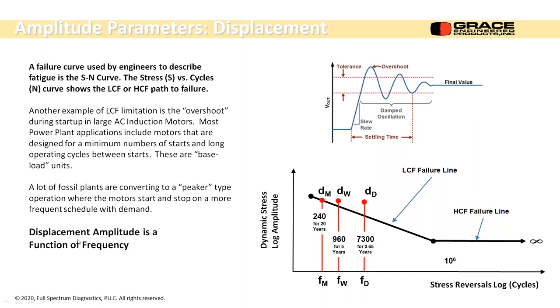Well, now these plants are starting to be used as peaker units. So natural gas plants are taking more of a baseload capability. They're turning on and off fans in fossil plants to adjust for load. What does that do? Every time we start or stop, we still have the same amplitude. We're not following that allowable curve anymore. So we'd have four times as many starts. So 960 starts. So instead of 20 years of life, we'll get 5 years of life. If we do that every day, we get a ridiculous amount of starts and stops. 7,300, that's about 7 to 8 months of operating.